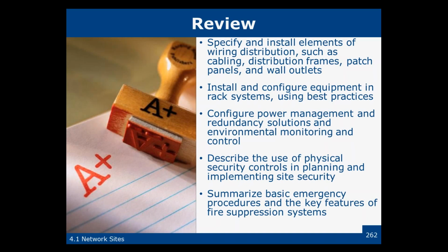Servers are placed back to back, not front to back, so that the warm exhaust from one bank of servers is not forming the intake air for the other ones. If you think about it, that makes sense, so that you don't blow the hot air of one machine into the intake of the other machine so that it becomes even hotter. So you put them back to back, and that creates the hot aisle.